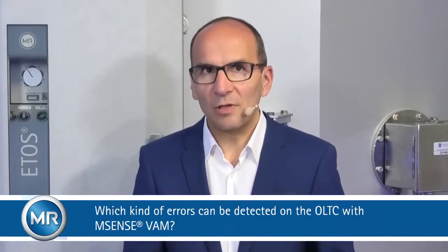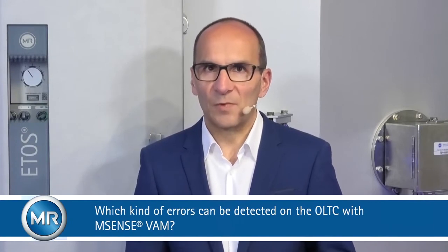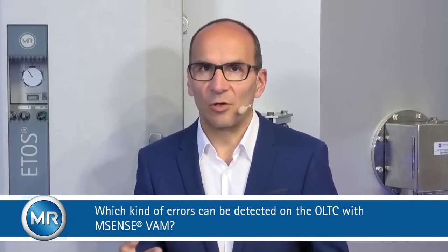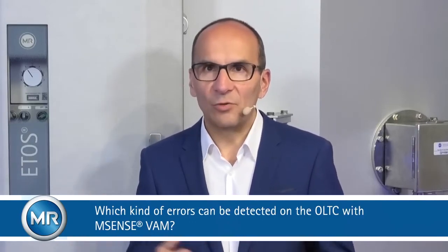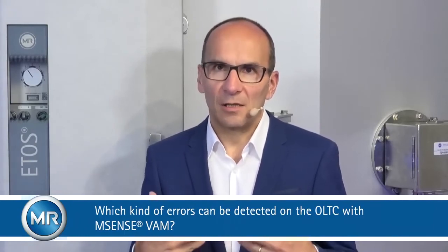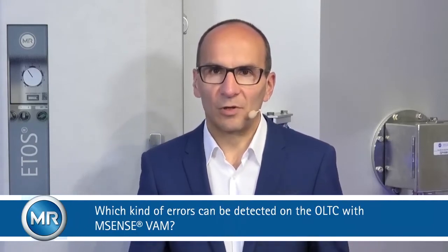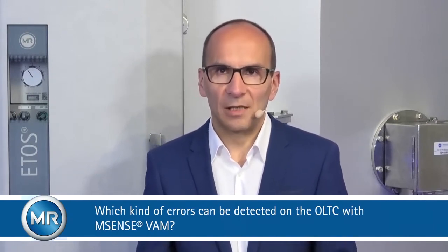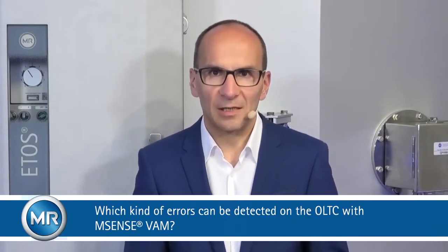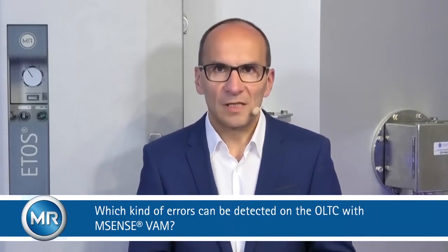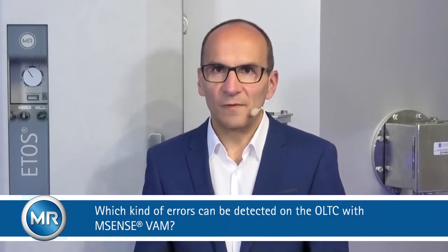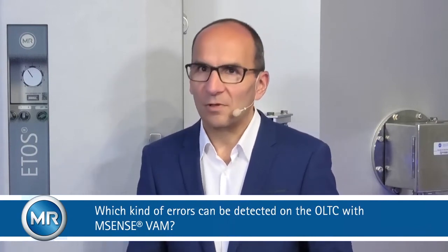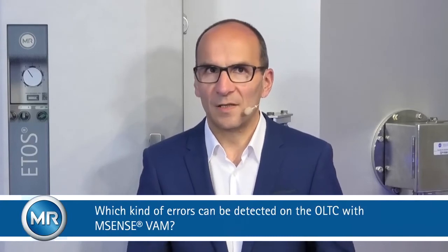But I think the most important aspect is something which comes with any monitoring system, is that it records and detects slow changes and helps you as operator in preparing your network configuration to reduce the load and the criticality on that transformer, to prepare and dispatch work crews to investigate. So all in all, online VAM helps you in detecting slow-moving, fast-moving, timing issues and allows you to dispatch the proper work crews to do a further analysis.